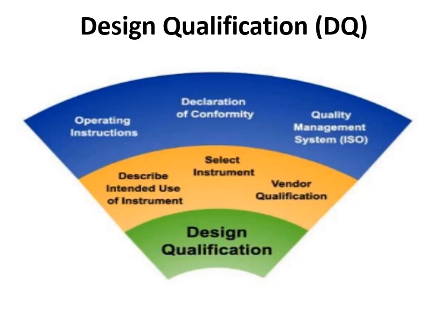Vendor qualification. Vendor is reliable. He is providing the appropriate thing according to the requirement. Select instrument. For design qualification, this is also important that you are selecting the proper instrument according to your requirements, according to your procedure, according to your product, and describe intended use of the instrument and tell how you are going to use your instrument.